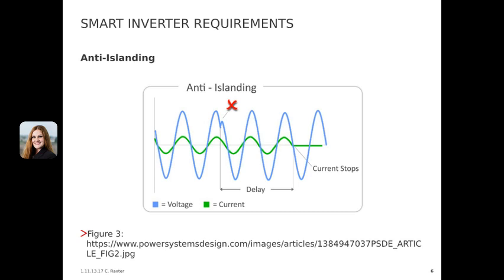Anti-islanding is a requirement for all DERs to ensure that there won't be an islanding event. To explain that a little more, if the inverter is in operation and the grid is removed, and the loads at the inverter terminals are equal to the inverter instantaneous production, then the inverter may remain in operation. This scenario is called islanding, and it is not desirable for lineman safety. Additionally, an islanding scenario could potentially damage customers' equipment in the event of an outage.